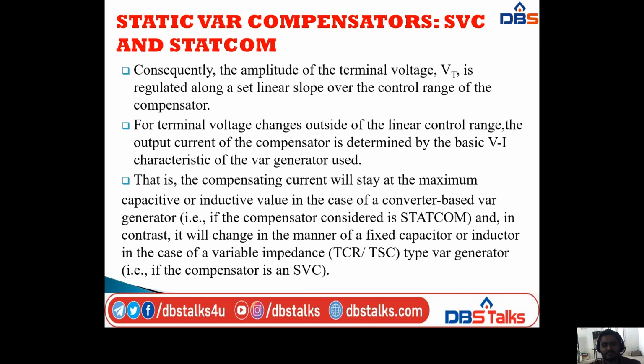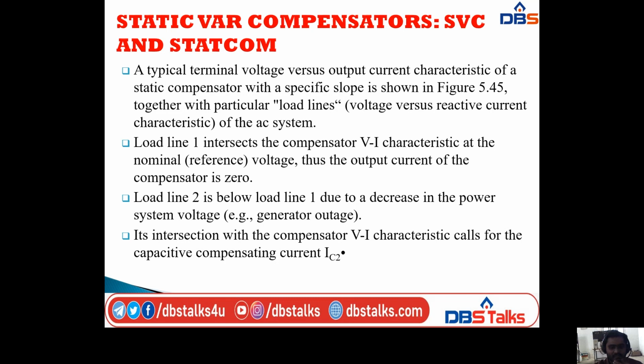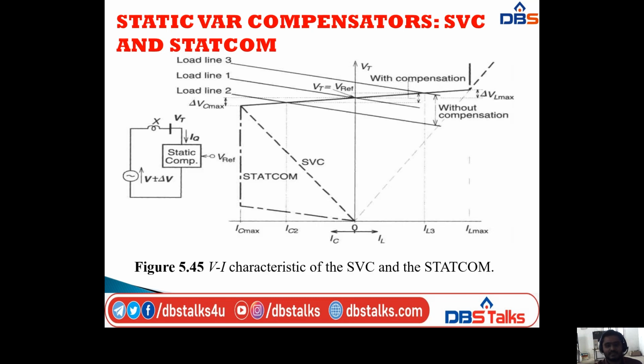Okay, so for the STATCOM, the compensating current will stay at the maximum capacitive or inductive value, and in an SVC, it will change in the manner of a fixed capacitor or inductor, in the case of a variable impedance type var generator, that is SVC. Next, a typical terminal voltage versus output current characteristic of a static compensator with a specific slope is shown in this diagram. So this gives the V-I characteristics of the SVC and STATCOM.